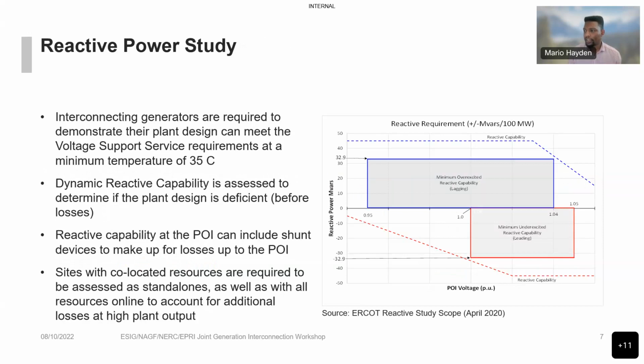The reactive power study is required by ERCOT—the generator must provide this study, usually through consultants or in-house expertise, based on ERCOT's recommendations and requirements. At a high level, it requires that you meet voltage support service at a minimum of 35 degrees Celsius, and addresses whether your project has dynamic reactive capability to connect, and whether it's deficient before losses. It also gives a broader idea of reactive capability, allowing use of shunt devices to make up for losses up to the POI.